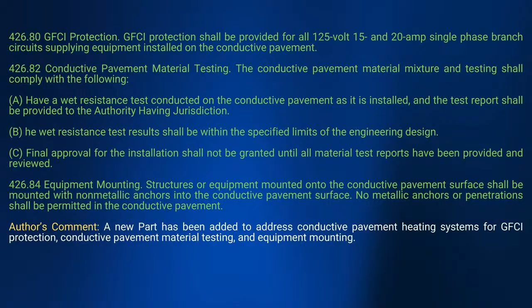It's a conductive pavement heating system. If it's snow melting, I don't see why you would need personnel protection. It's a new type heating system, I guess, that they're coming in with. But they don't want anything metal on it, because if you look, even when I get into the equipment mounting, it tells you structures or equipment mounted onto the conductive pavement surface shall be mounted with non-metallic anchors into the conductive pavement surface. I don't understand the personnel protection requirement in there. That's interesting. I'll have to do some research on that.